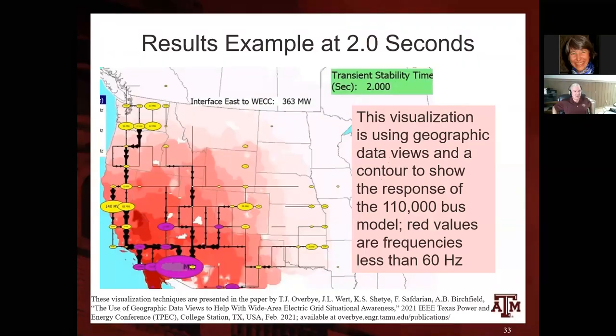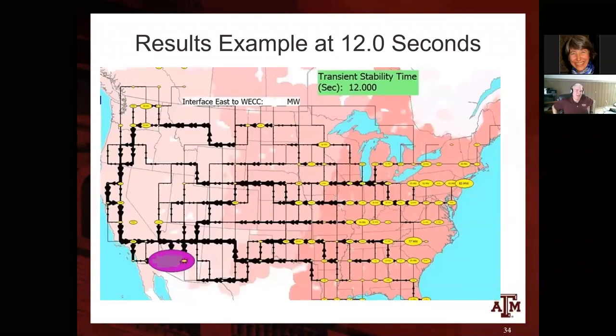If it was just the West by itself, it would just drop in the West. But since it was also involving the East, at 2 seconds in, the frequency is just starting to fall in the East. At 12 seconds in, the frequency disturbance has propagated across the whole country, but it's very modest—you can't tell that from the graph, but it is very, very modest. It's like the East barely takes notice, except all the generators across the East have sensed within a few seconds that there was a problem in the West, and they're immediately sending aid.